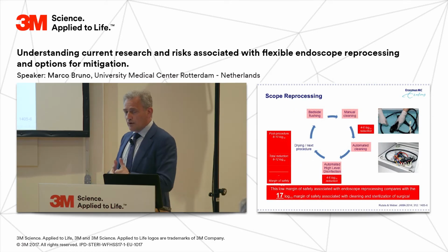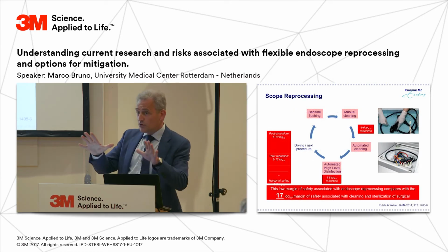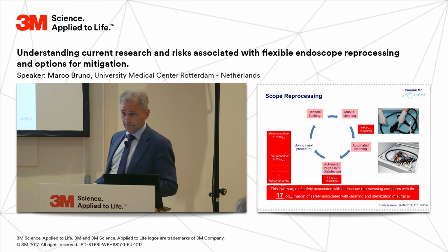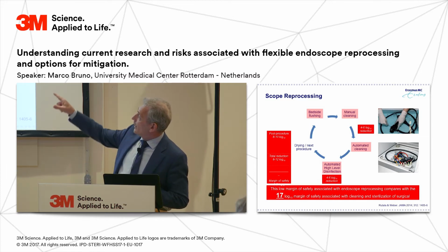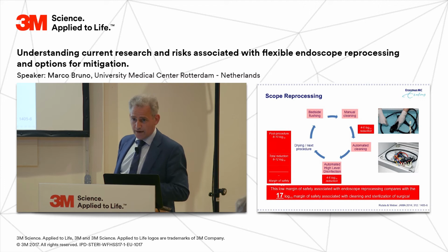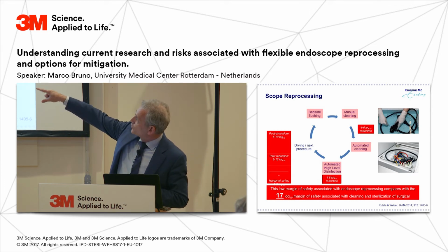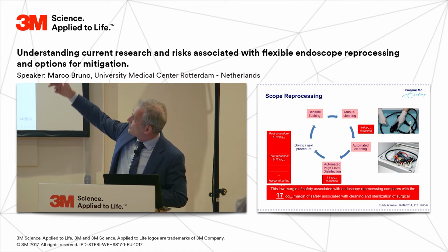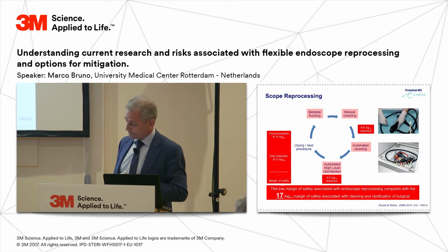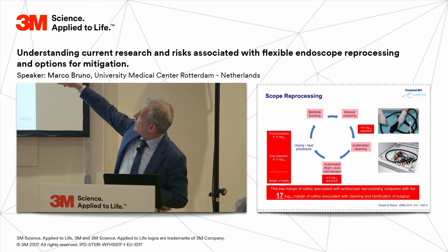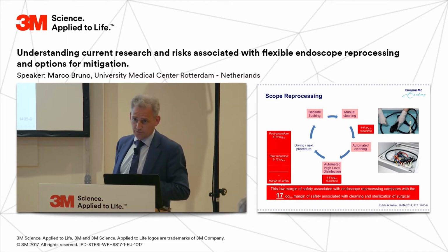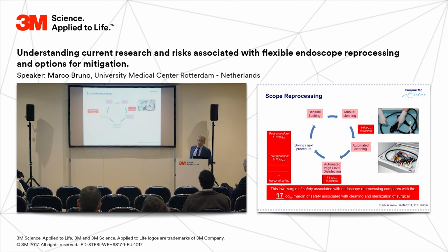Now, if you look at scope reprocessing, I find this a very interesting slide. Maybe you know this. For me, this was a revelation, to be quite honest. Because if the scope comes out of the drying cabinet and you have used the scope in a patient, then you have post-procedurally about an 8 to 10 log10 bioburden. Then you start with the manual cleaning process, very important, one of the most important steps in the whole cleaning process. And then you're able to have a 4 to 6 log10 reduction of that original bioburden.